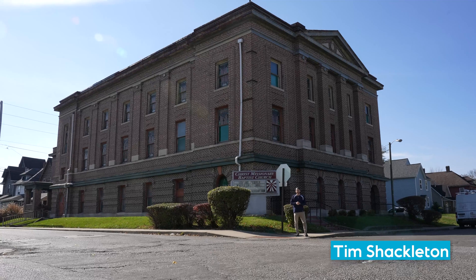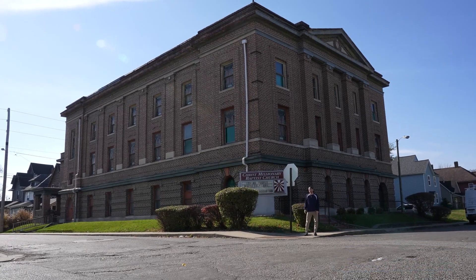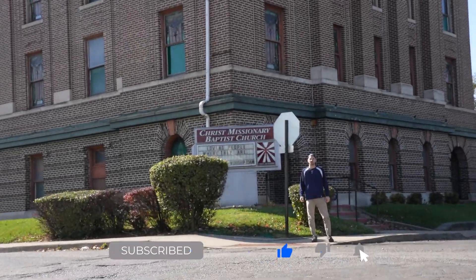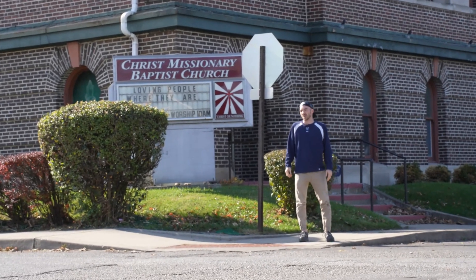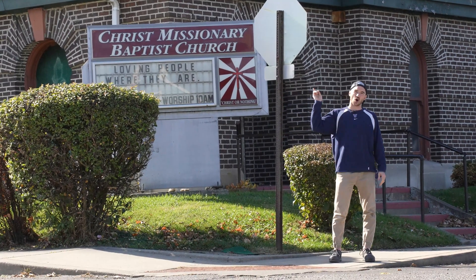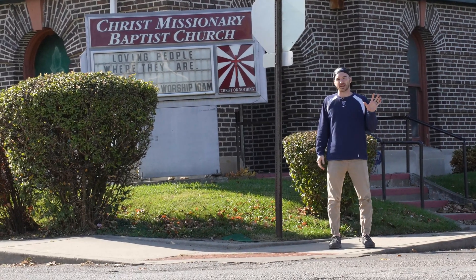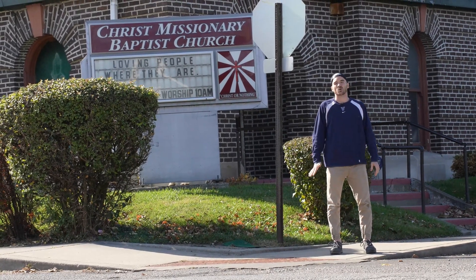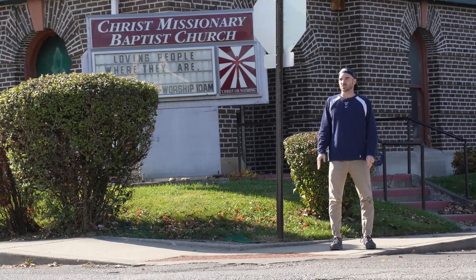I'm Tim, ePro Apprentice and Project Manager. We're here at Christ Missionary Baptist Church, established in 1919, relocated to this building in 1955. They've got a three-phase commercial service, as most churches do, and they need a service upgrade. There is a massive 100-foot-long run across the attic space of the church to their main two-panel setup that we need to figure out. We need to limit the number of bends going to our meter base and the other existing equipment.